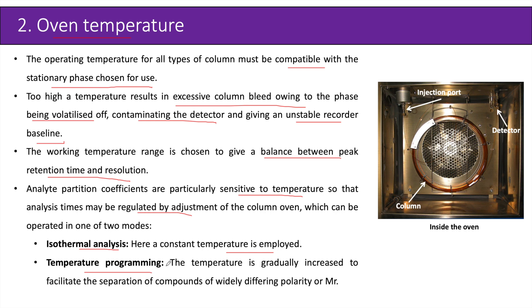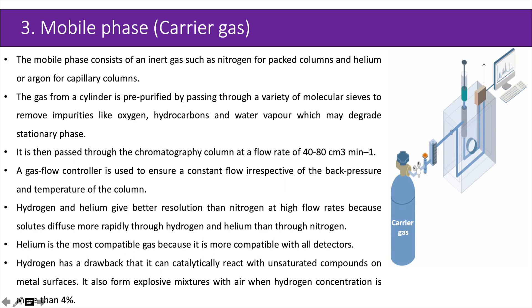The second mode is temperature programming, where the temperature is gradually increased to facilitate the separation of compounds of widely differing polarity or molecular weight. The mobile phase consists of an inert gas such as nitrogen for packed columns, or helium or argon for capillary columns. The gas from a cylinder is pre-purified by passing through a variety of molecular sieves to remove impurities like oxygen, hydrocarbons, and water vapor, which may degrade the stationary phase.